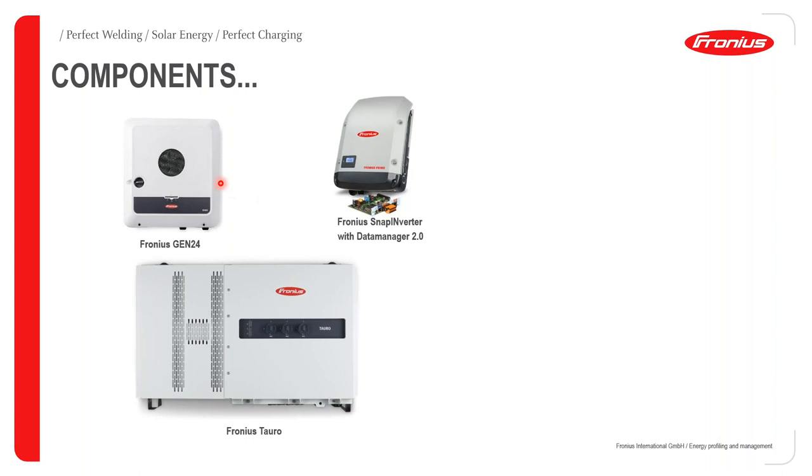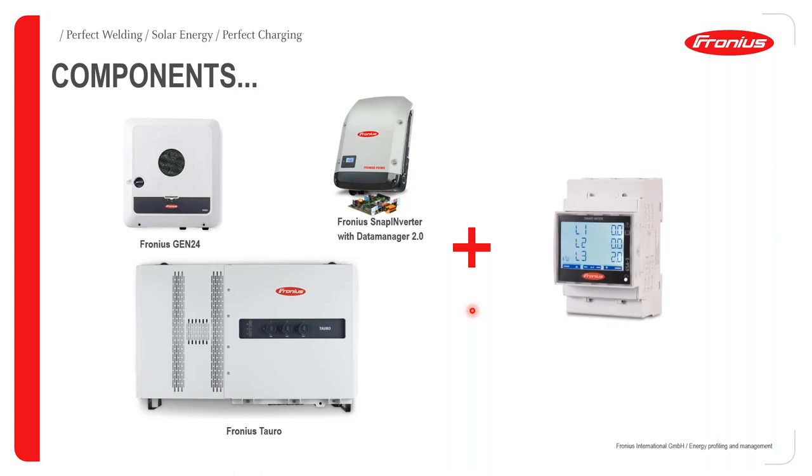Looking at the required components: it's basically a Snap inverter with a data manager. You would need the data manager to connect to the smart meter and be able to effect feed-in limitation. For the Gen24 Plus and the Tauro inverters, these latest products all have integrated the pilot, which is the data communication equivalent of the data manager. You will also need a smart meter to be able to effect feed-in limitations.